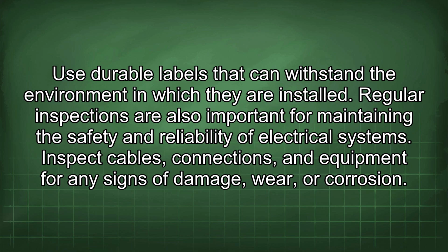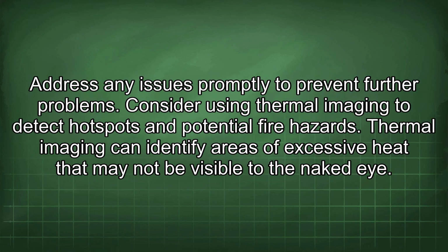Regular inspections are also important for maintaining the safety and reliability of electrical systems. Inspect cables, connections, and equipment for any signs of damage, wear, or corrosion. Address any issues promptly to prevent further problems. Consider using thermal imaging to detect hotspots and potential fire hazards. Thermal imaging can identify areas of excessive heat that may not be visible to the naked eye.